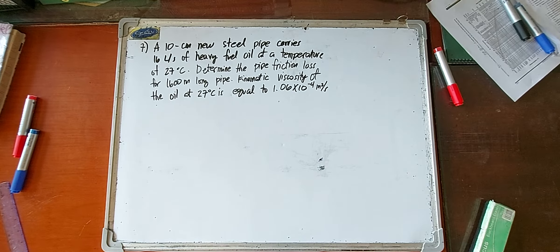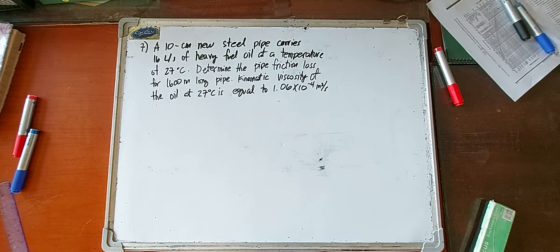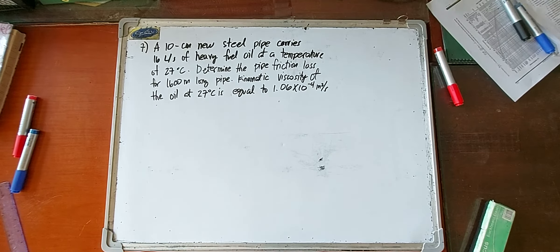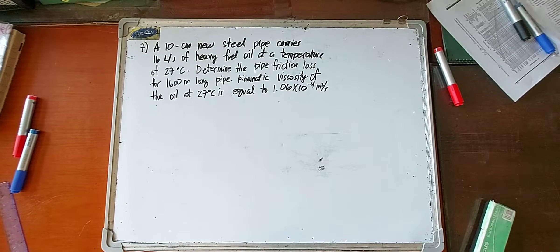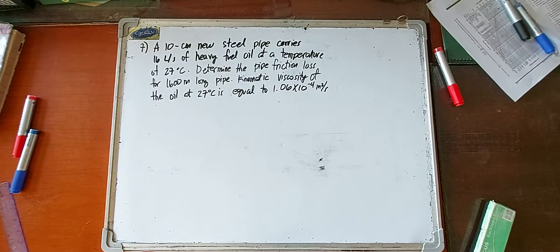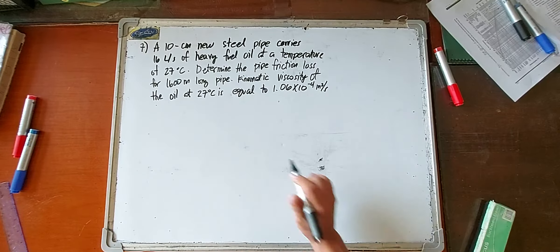Let's solve number seven. A 10 cm new steel pipe carries 16 liters per second of heavy fuel oil at a temperature of 27 degrees Celsius. Determine the pipe friction loss for a 1600-meter long pipe. The kinematic viscosity of oil at 27 degrees Celsius is equal to 1.06 times 10 raised to negative 4 square meters per second.